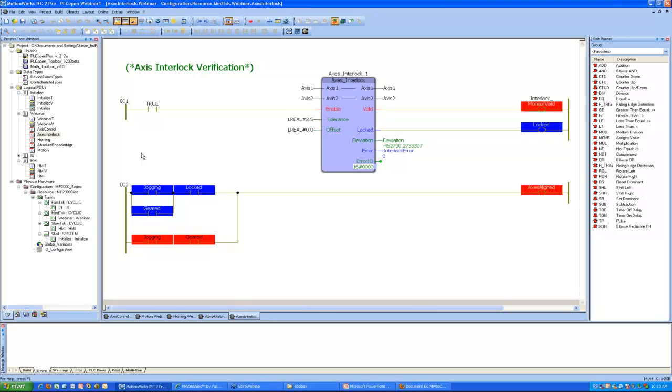There was one question at the end asking about the reset Mechatrolink in conjunction with an MP2600. And that is a limitation right now of the MP2600. The Y reset Mechatrolink function block does not work on that hardware platform, because to reset the amplifier would actually cause a soft reboot of the option card or the MP2600 as well. So it's very different behavior than would be experienced on the MP2300 system with Y reset Mechatrolink.